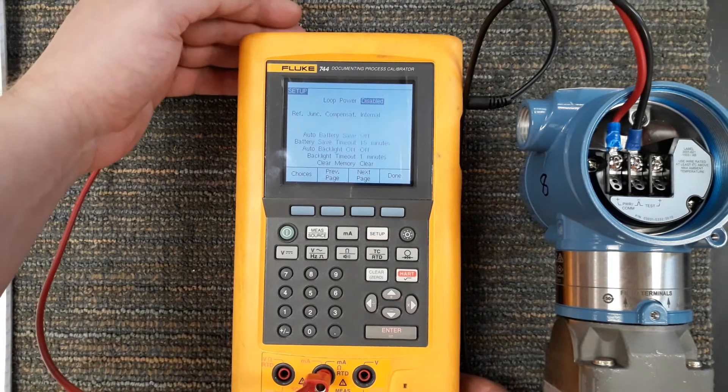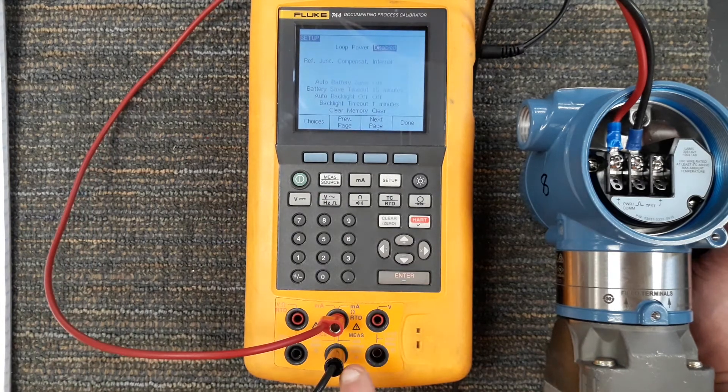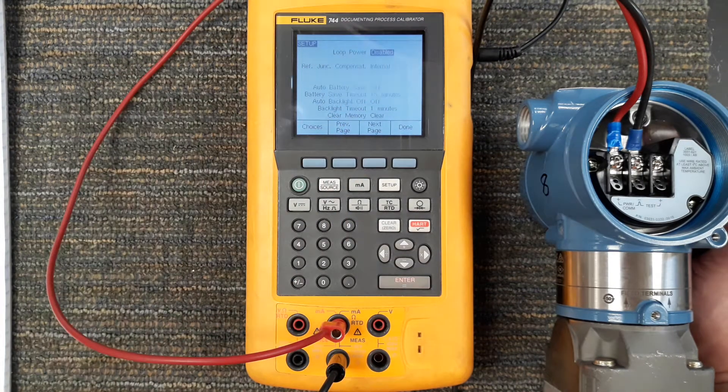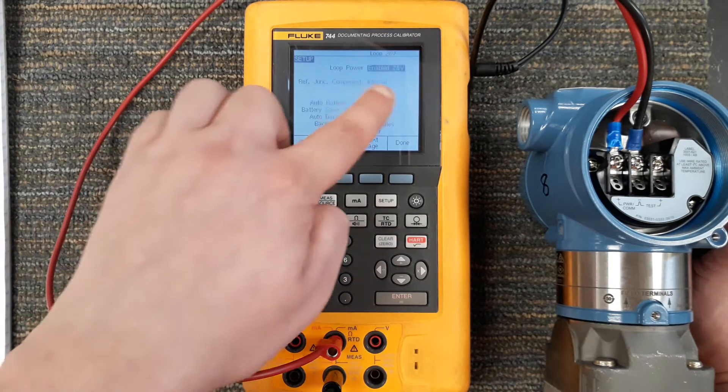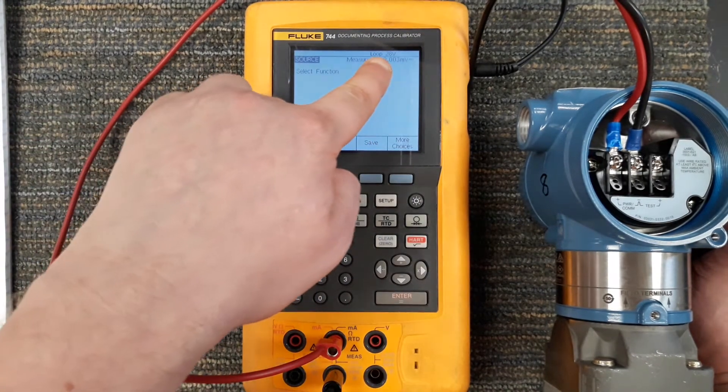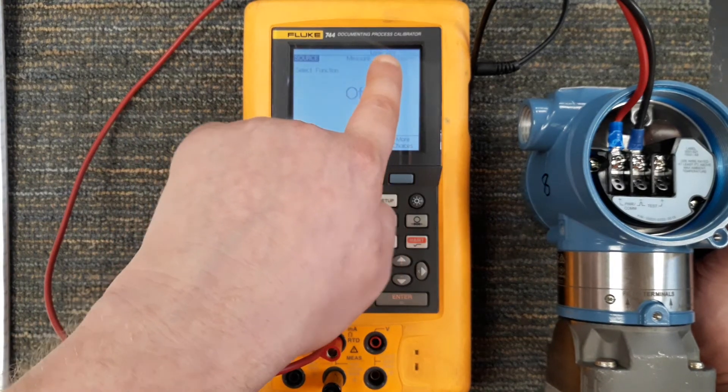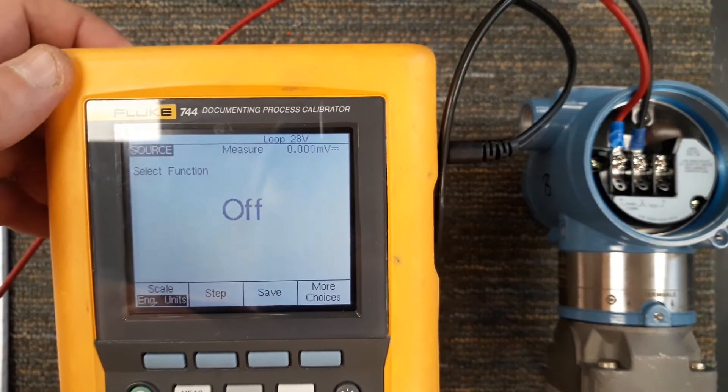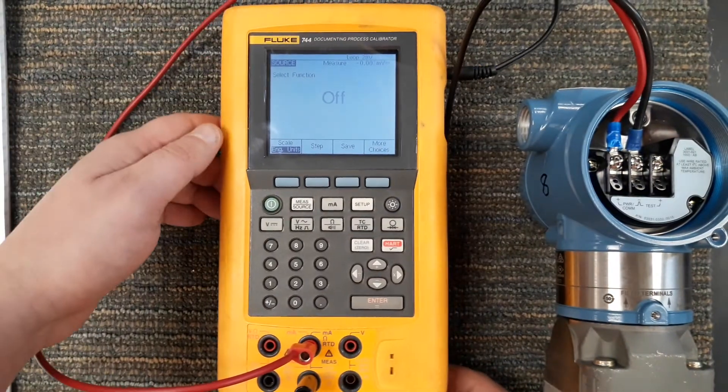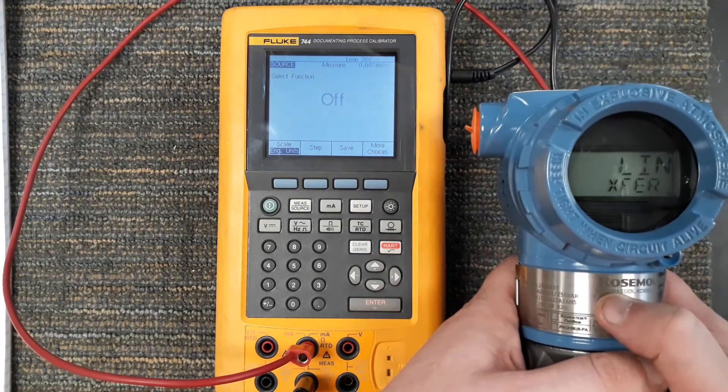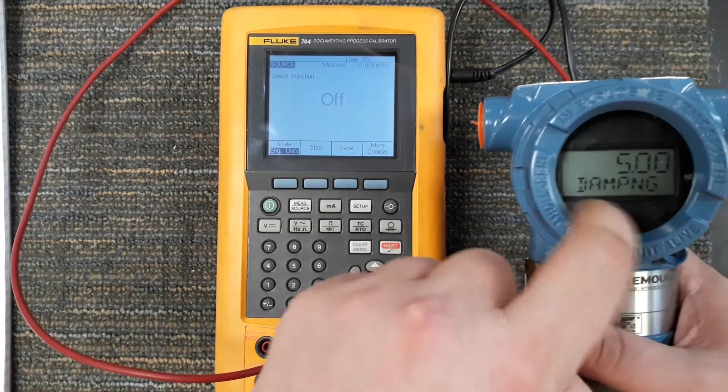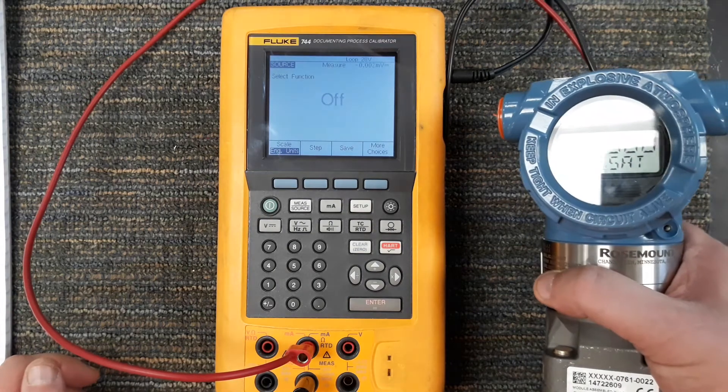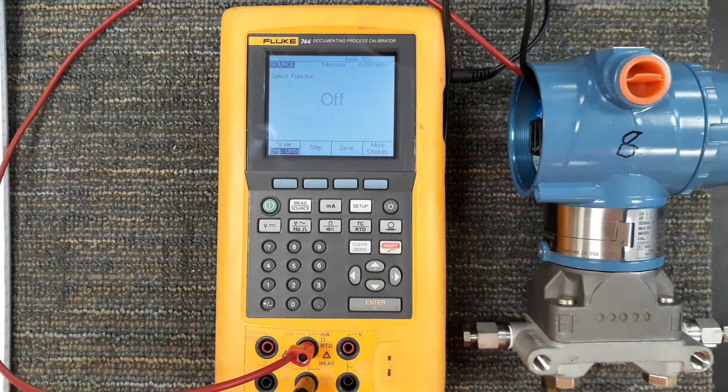Again we're on the current ports sourcing current which is for providing loop power. I'm gonna go ahead and hit enter on this, go down to 28 volts, hit enter. Now loop power should be enabled. I'm gonna hit the done button to go back to the screen I was at. If you look at the very top, this also gives me a visual indication that loop power is currently on, 28 volts. And if I flip this over now all of a sudden you can see the differential pressure transmitter is powered up, my display is working and it's cycling through showing me all the information I need to know. That's the basics of loop power.